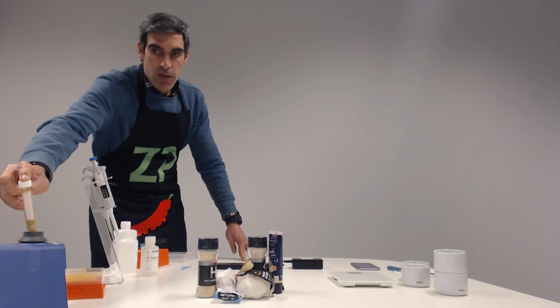Once this is done, I will close the centrifuge tube and I will vortex it. In this instance, you should vortex it for 1 minute and let it rest for 5 minutes. However, for the sake of this demo not to be too long, I will reduce those times to vortexing it for 30 seconds and letting it rest for 2 minutes. The important thing is that you follow the same procedure for all the samples that you are sampling and want to compare. So this is about 30 seconds.